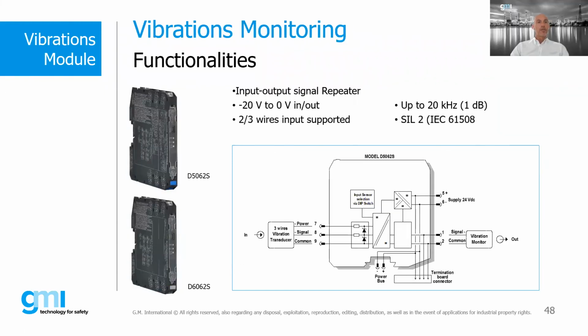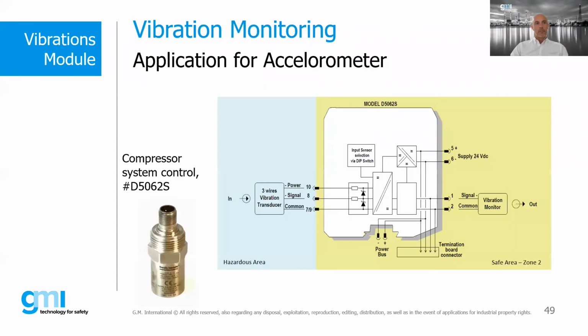We also have vibration monitoring applications, for motors or turbines, where there are vibration transducers that send a specific standard signal, from minus 20 up to 0 volt, with 2 or 3 wire supported. We probably have a slide where we explain a little bit about this application, Massimo.